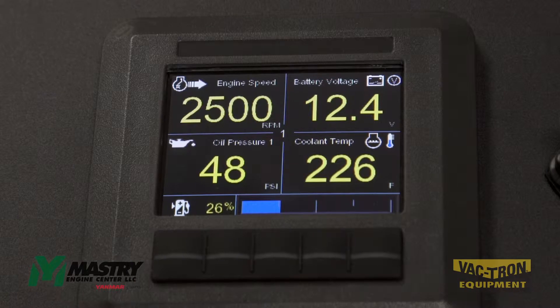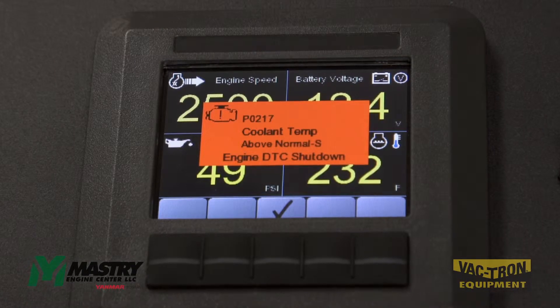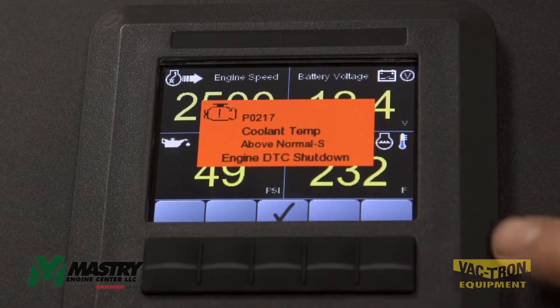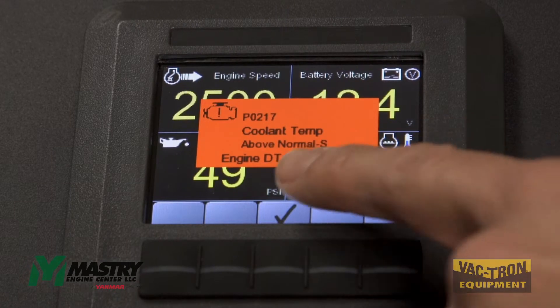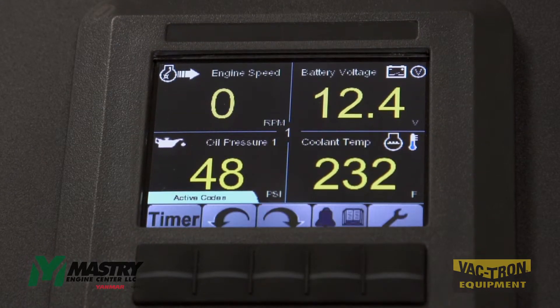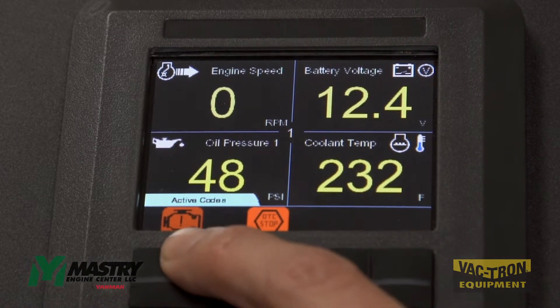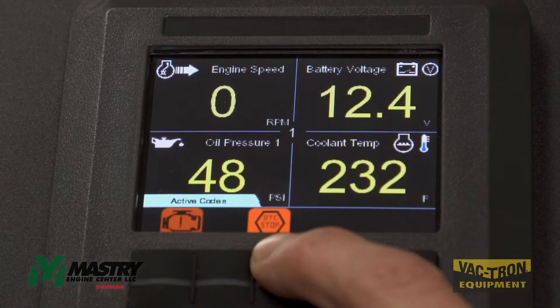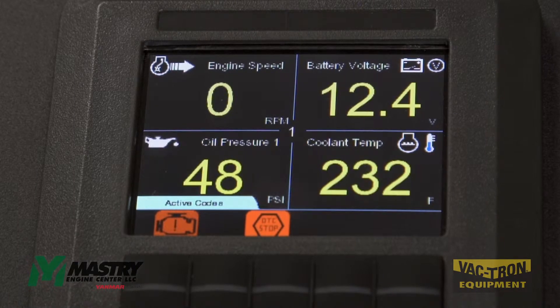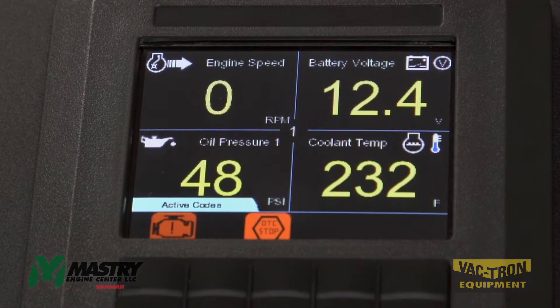If the engine temperature exceeds 230 degrees Fahrenheit, you will get a diagnostic trouble code for high coolant temperature, and the engine will shut down in order to protect the engine. A fault code like this will pop up, and what's different about this fault code versus a regular fault code is the text at the bottom that says 'engine DTC shutdown.' You can acknowledge this fault code and then you'll see the engine speed has dropped to zero. Now we have an active fault code icon, but we also have a DTC stop icon indicating that this particular fault code has shut down the engine. The two fault codes that can shut down the engine are coolant temperature fault codes and a low oil pressure fault code.